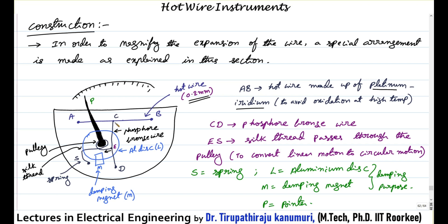The spring tries to pull the silk thread downwards. There is one aluminum disk used along with a damper magnet. This aluminum disk is directly connected to the pulley. Whenever the pulley or the pointer moves, this aluminum disk also moves, cutting through the flux of the permanent damping magnet, producing the required damping torque.